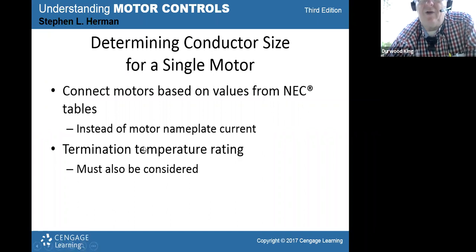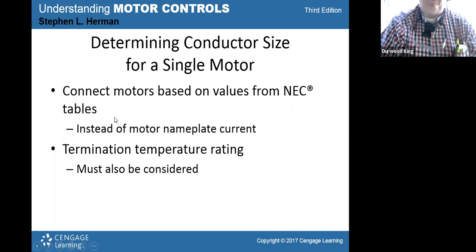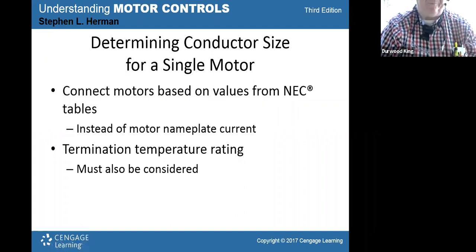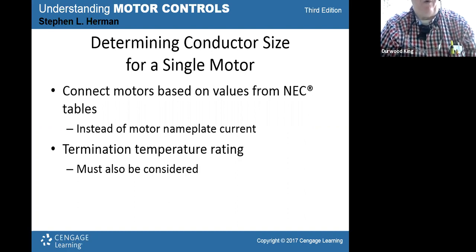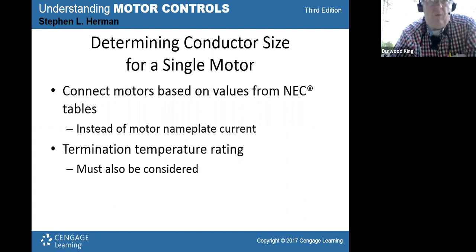So you pick the wire size or conductor size based on the National Electric Code tables that we just looked at. Instead of looking at the nameplate current, you actually get the value out of the code book for picking the wire size. The reason for that is this. You may be running a Baldor motor today, but you may end up with a Leeson in a year from now. So they get a middle of the road number from different brands, and what's in the code book would represent an average of motors, if that makes sense. So your nameplate could vary, but a Leeson or a Baldor may vary slightly, but the code book will cover you for either one of them.